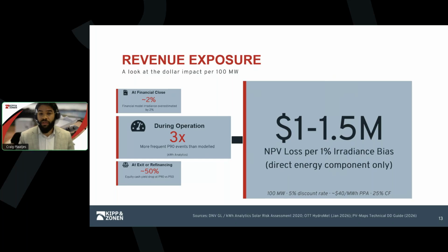That's the high level estimated cost of 1% measurement error in pure energy terms. And it maps very closely to a case study we presented in our blog earlier this year, where we showed a 64 megawatt plant with a 4% PR deviation incurring about $1.8 million losses over 30 years.